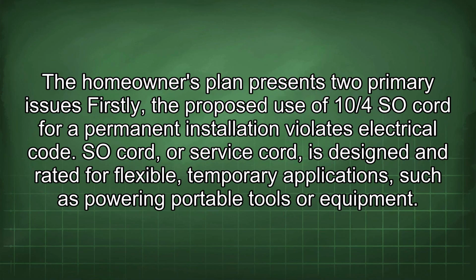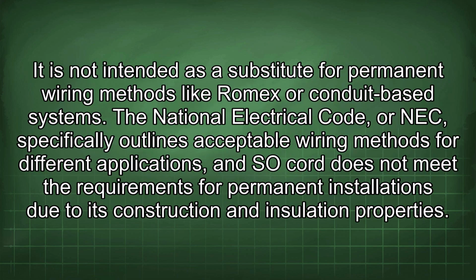The homeowner's plan presents two primary issues. Firstly, the proposed use of 10/4 SO cord for a permanent installation violates electrical code. SO cord, or service cord, is designed and rated for flexible, temporary applications such as powering portable tools or equipment. It is not intended as a substitute for permanent wiring methods like ROMEX or conduit-based systems.